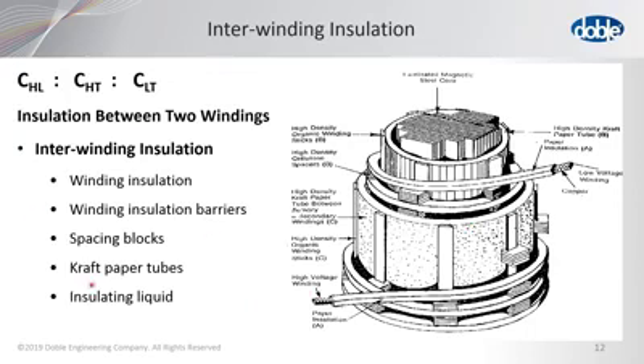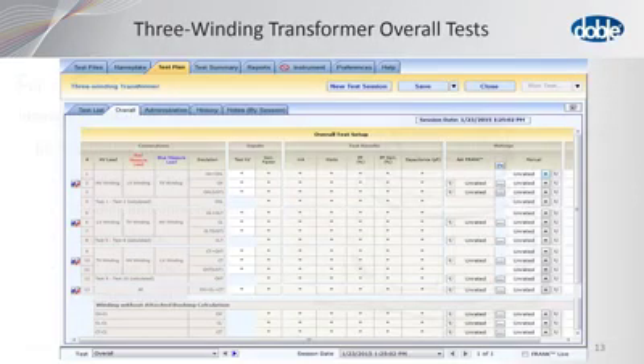The Kraft paper tubes are these large cylinders here, and the insulating liquid. Notice there are no bushings, no load tap changer in this, because those are not part of those tests of insulation. So it's good to be able to know what is in the test that you are doing. All right, now DTA, or Doble Test Assistant, is used to make sure that we get consistent test results. And this is the form that we use.